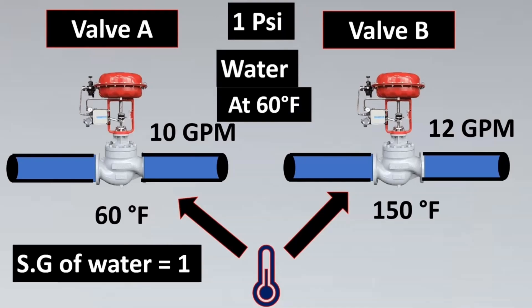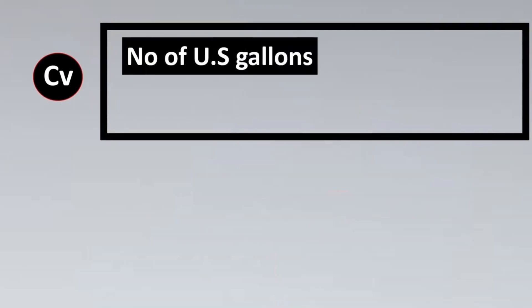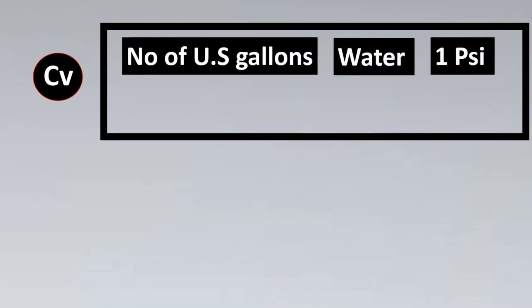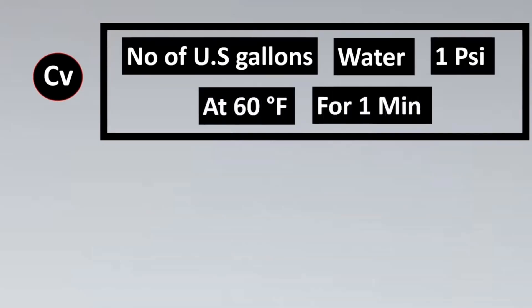We have three standard parameters: the psi drop is 1 psi, water is the fluid, and temperature is 60 degrees Fahrenheit. The definition of CV is the number of US gallons of water that can flow through a valve with 1 psi pressure drop at 60 degrees Fahrenheit for 1 minute.